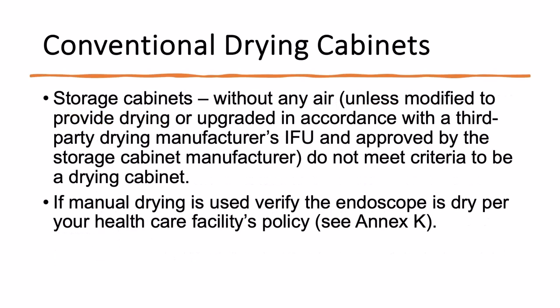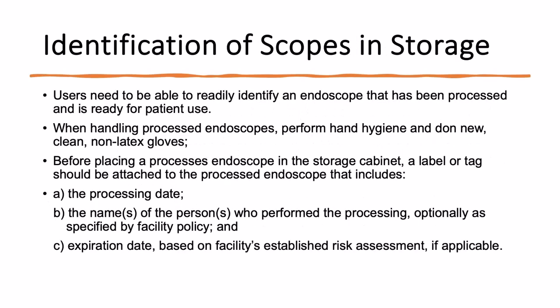Storage cabinets without any air, unless they're modified to provide drying or upgraded according to a third-party drying manufacturer's instructions and approved by the storage cabinet manufacturer, do not meet criteria as a drying cabinet. If manual drying is used to verify the endoscope is dry, according to your healthcare facility's policy, make sure you follow Annex K, which shows you the manual drying process.